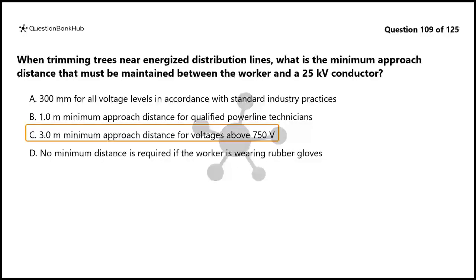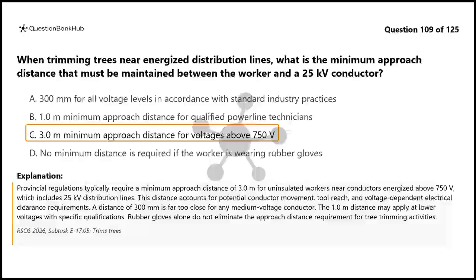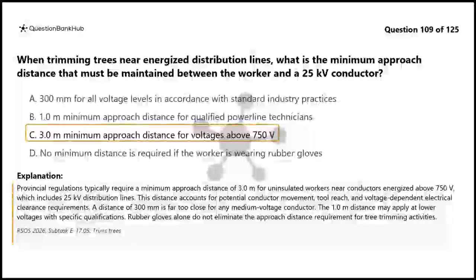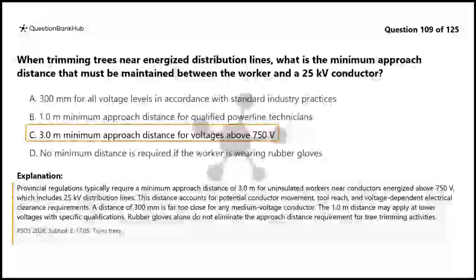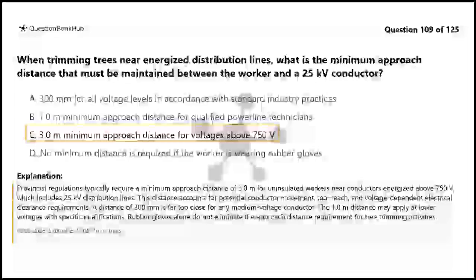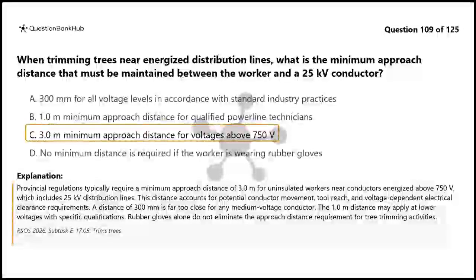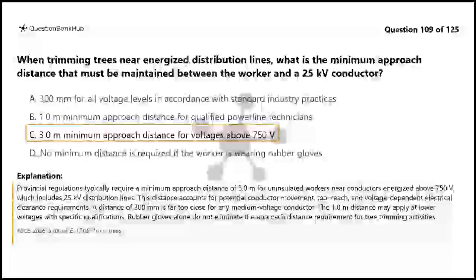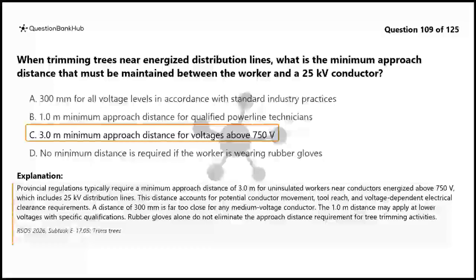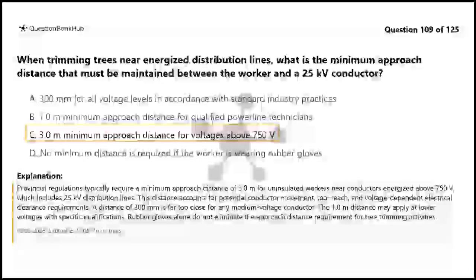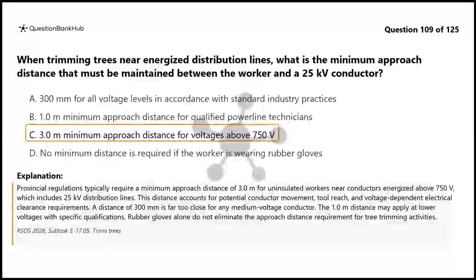The correct answer is C. Provincial regulations typically require a minimum approach distance of 3.0 meters for uninsulated workers near conductors energized above 750 V, which includes 25 kV distribution lines. This distance accounts for potential conductor movement, tool reach, and voltage-dependent electrical clearance requirements. A distance of 300 mm is far too close for any medium-voltage conductor. The 1.0 meters distance may apply at lower voltages with specific qualifications. Rubber gloves alone do not eliminate the approach distance requirement for tree trimming activities.